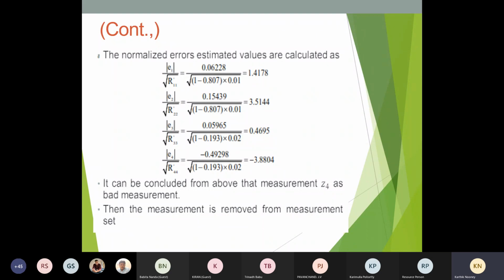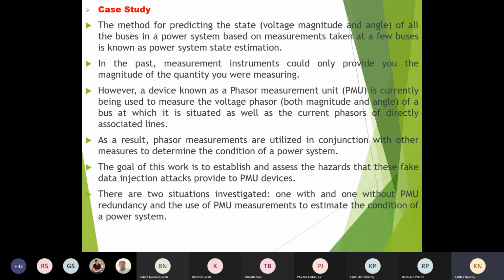Like this, we can easily estimate from a complex network, by feeding all the voltages and powers to this simple set of programs, exactly where the bad data is. It depends upon the calculation of the threshold value. It will give you that bad data indication itself in the program. So in the case study here, first we calculate all the state voltages in the non-linear phase, then those are transformed into PMU data after the post-processing stage, and then we combine the state estimation with PMU. That's what is said here.